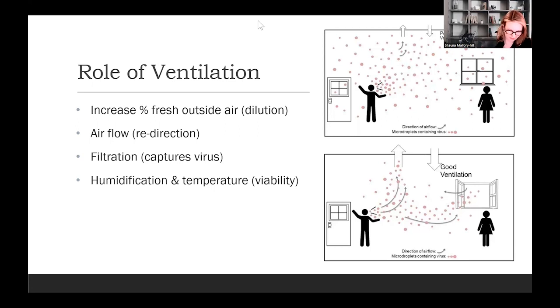Therefore, the very first role of a ventilation system is to exhaust polluted air and provide more clean air and dilute the viral load in the space. The other thing that mechanical ventilation can do for you is redirect or produce airflow in the space. And generally, we want that airflow to be going out of the breathing space and into and above us, and to be exhausted above us and out of the room. The other role of a ventilation system is to provide filtration and to capture the virus and clean the air. And fourthly is humidification and temperature control, which has an impact on the viability of the virus in this aerosolized form.